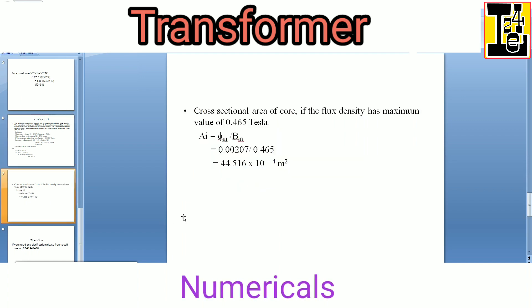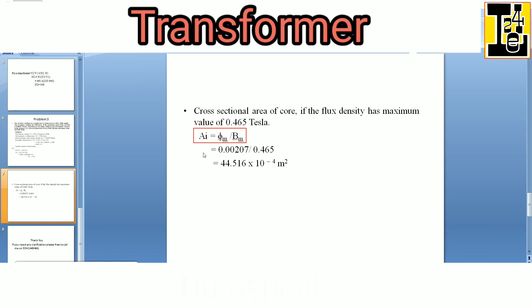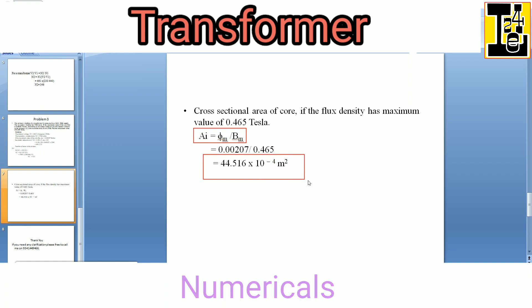The third bit is calculating the cross sectional area of the core if the flux density has maximum value of 0.465 tesla. We have the formula: the net cross sectional area AI is equals to φm divided by Bm, where φm is the maximum flux and Bm is the maximum flux density. Substituting the values, we get the cross sectional area AI is equals to 44.516 into 10 raised to minus 4 meter square. So this is the solution for problem number 3.